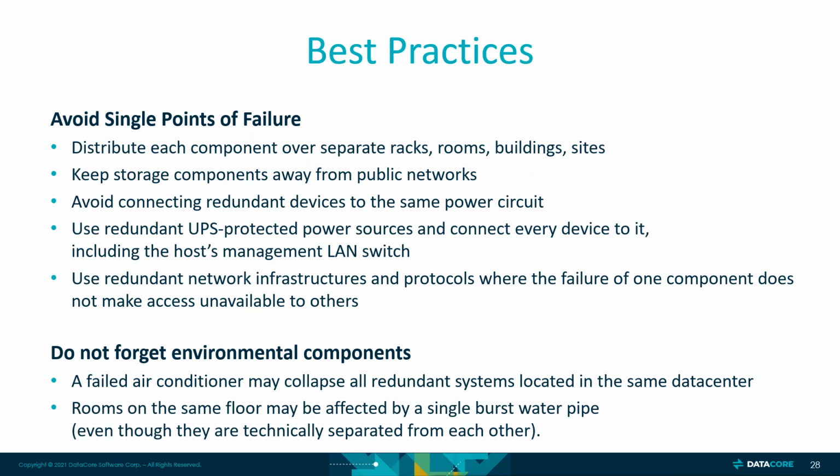More frequently than I would have expected, we find folks who look at the underlying hardware but fail to take into account the environmental components. They don't realize that, hey, if that air conditioner fails and things start heating up in here, and both of those systems, redundant systems, are sitting in the same location, they both went out. So you've got to watch out for things like this. We've seen lots of incidents of this bursting water pipe right above the same location, where they thought they were providing the separation for different fault isolation, and in fact were subjected to the same environmental hazard.